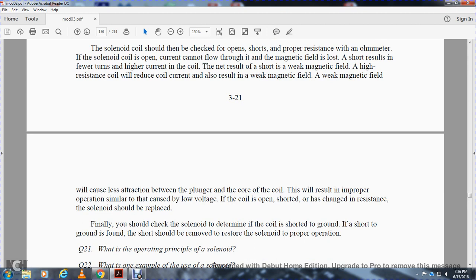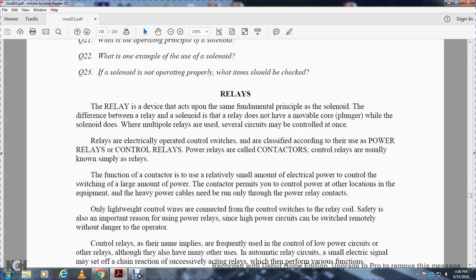Finally, you should check the solenoid coil to determine whether it is shorted to ground. If a short to ground is found, the short should be removed to restore the solenoid to proper operation.